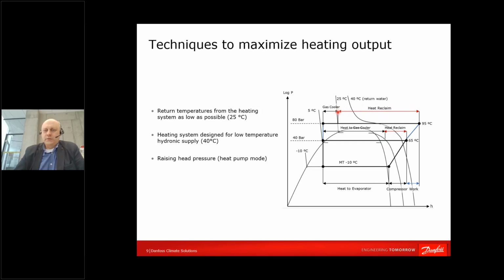Therefore, we started discussions with our supermarket chains, with people responsible, with designers, and it also goes hand in hand with district heating utilities, the imagination about low temperature district heating, so that systems, air handling units or something else should be designed for low temperatures. Instead of using 80 supply, 60 return, we are speaking about 60 supply, 30 return. So we are speaking about larger delta T and lower temperatures.